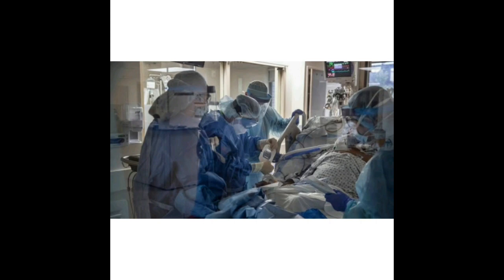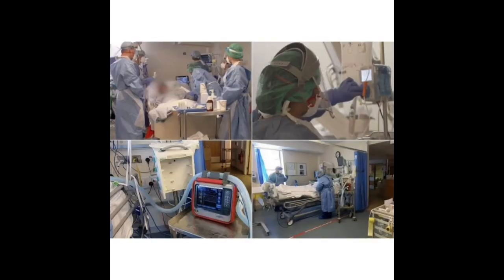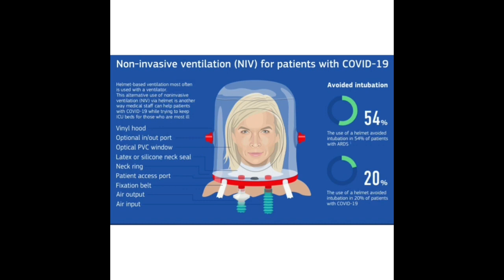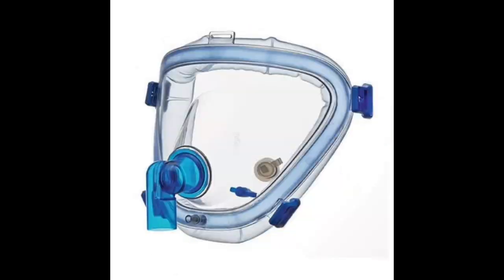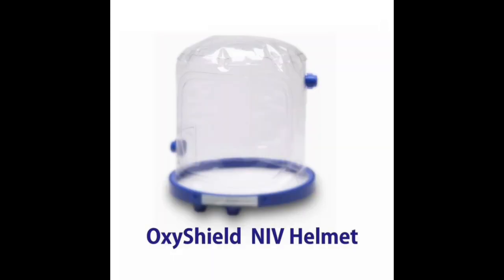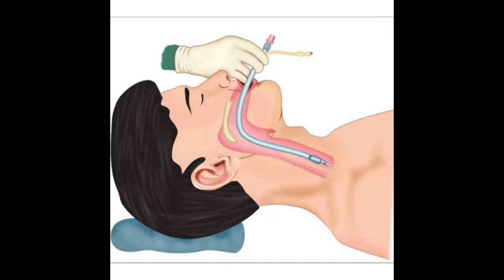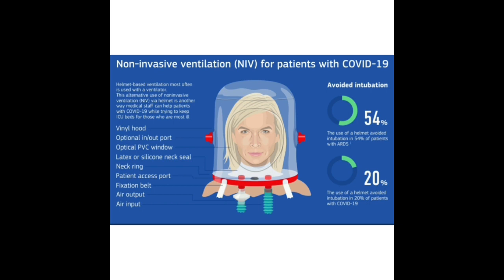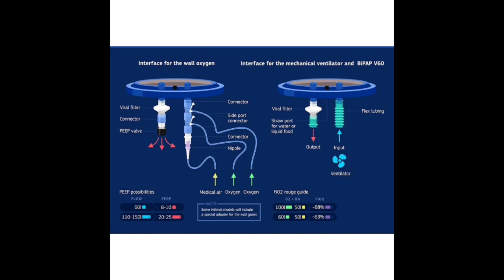In such situations, the best alternative method to handle is non-invasive ventilation. Non-invasive ventilation is the delivery of oxygen via a face mask or helmet, and therefore eliminating the need of an endotracheal intubation. The helmet is a clear plastic hood that contains the patient's head and is joined to a hard plastic ring supporting a soft silicone collar. Two pipes connect the expiratory and the inspiratory limbs of the circuit to the ventilator or wall gas.